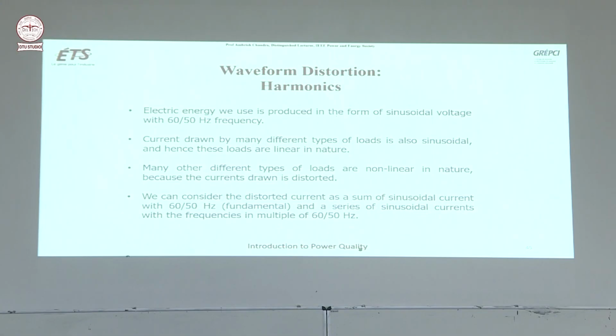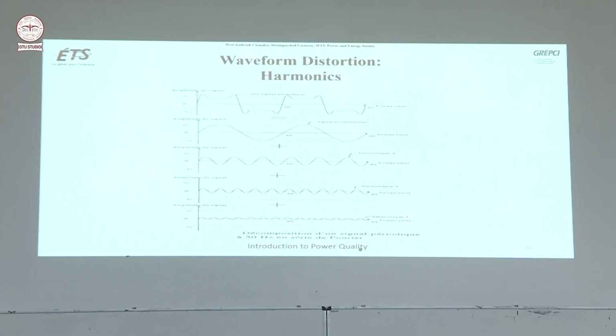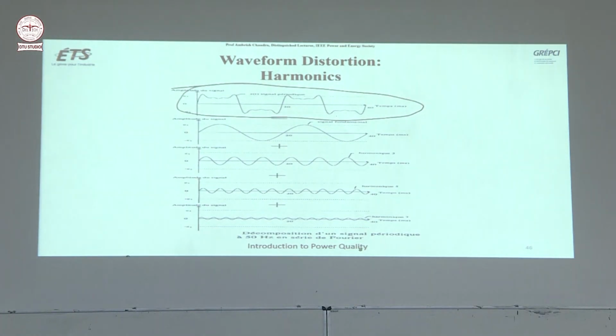Now the harmonics. In North America we have 60 Hertz, here you have 50 Hertz. Normally many loads are linear, but many different types of loads are non-linear in nature, so the current drawn is distorted. If you do the Fourier transformation, you will come to know. We will see here. Suppose you have this current. If you do the Fourier transformation, this is the fundamental component.